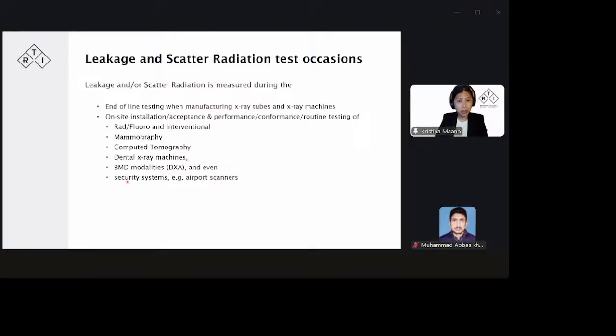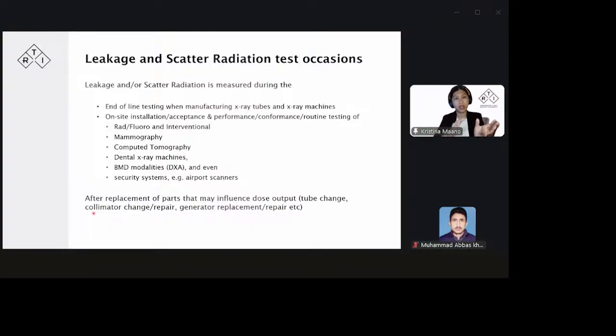Also, we would like to emphasize that scatter and leakage radiation testing should also be done in security systems, such as those airport scanners that we see during security check at the airport. Another instance where we do scatter and leakage testing is after the replacement of parts that may influence the dose output. So that's tube change, collimator change or repair, generator replacement or repair. Tube leakage and scatter measurements should be done during those occasions as well.